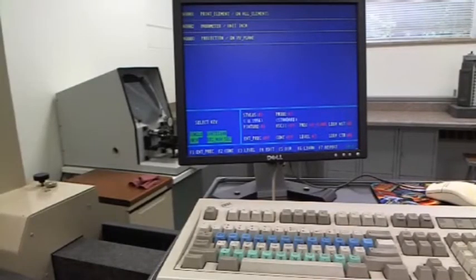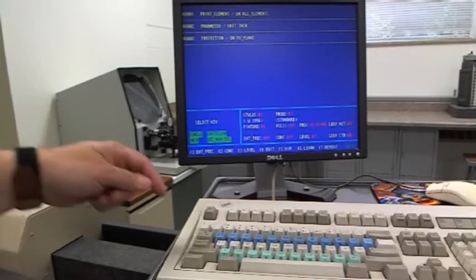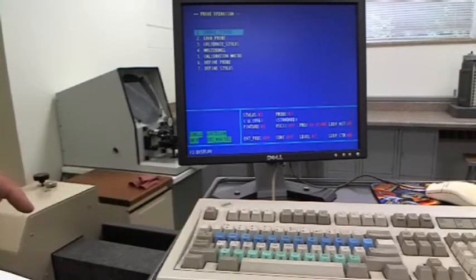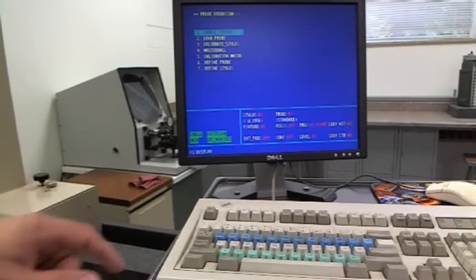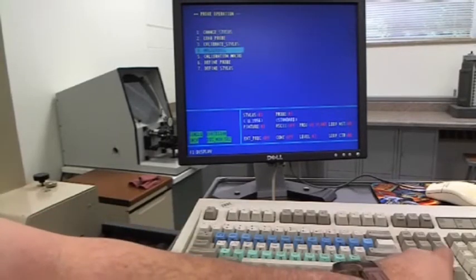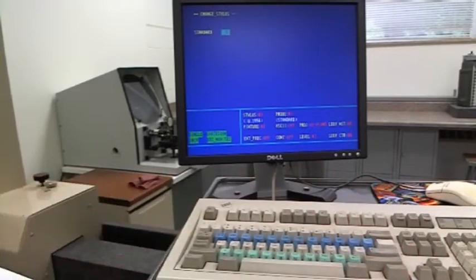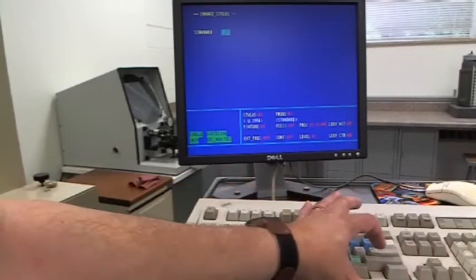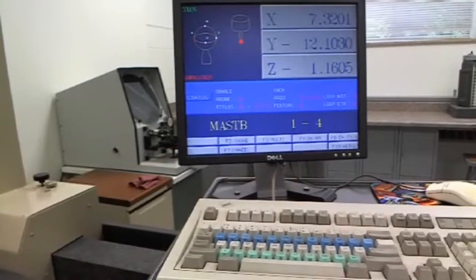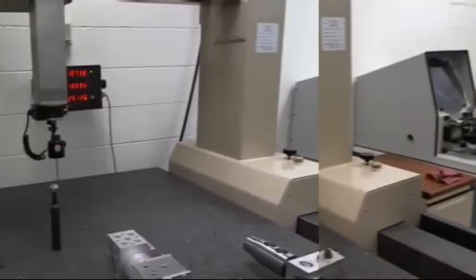The calibration of the stylus on the calibration sphere requires that we press the calibration button. We select calibration micro or macro. Standard, of course, is 1 in this case. And then we are encouraged to move the probe around the calibration stylus ball. And I'll move the camera around here so you can watch that.